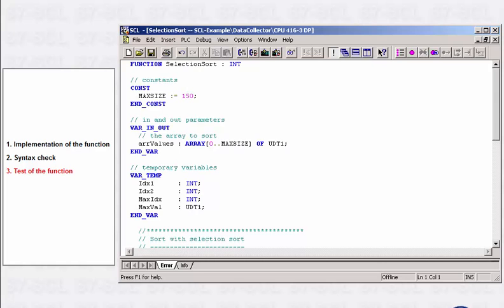The functionality should now be checked online, because often errors are only discovered during runtime. First, the S7-SCL block is loaded into the automation system. S7-SCL gives you two options for checking the functionality: Program Status and Single Step Mode to monitor variable assignment step by step.